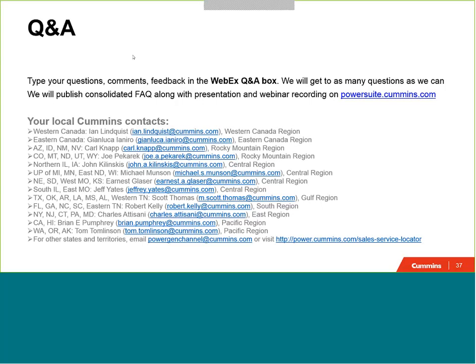Next question. How do you figure the right size load bank? Good question. I talked very briefly about this. Sizing the right size load bank really comes down to a couple things, and the biggest one being, how are you going to test the product? If you're looking at meeting the bare minimum requirements from NFPA 110, which says 30% load, and again, I think most generator manufacturers would agree that 30% load is the minimum we would like to see for regular testing, then it's as simple as taking 30% of the generator set standby rating. However, this limits you from doing anything outside of that standard testing.